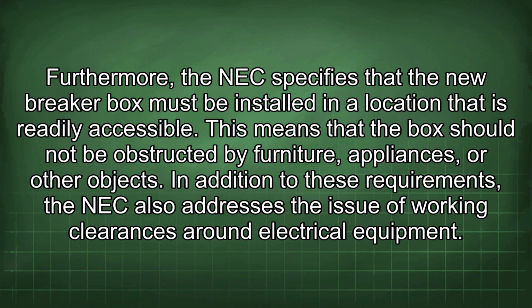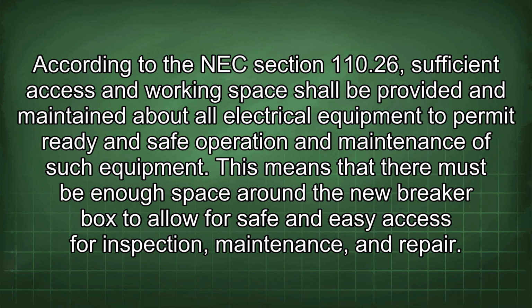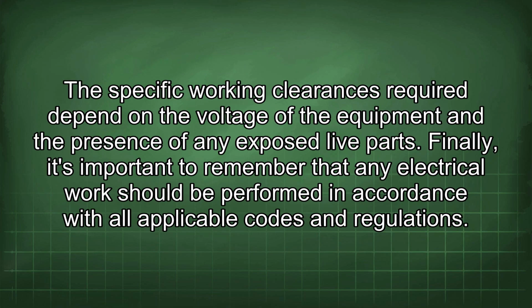In addition to these requirements, the NEC also addresses the issue of working clearances around electrical equipment. According to the NEC Section 110.26, sufficient access and working space shall be provided and maintained about all electrical equipment to permit ready and safe operation and maintenance of such equipment. This means that there must be enough space around the new breaker box to allow for safe and easy access for inspection, maintenance, and repair. The specific working clearances required depend on the voltage of the equipment and the presence of any exposed live parts.